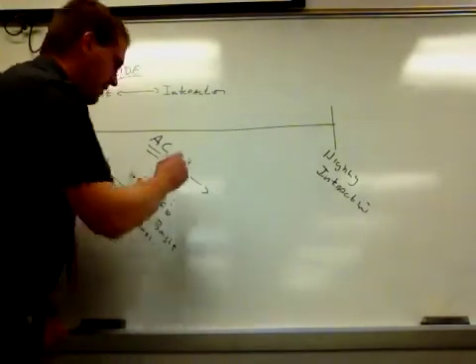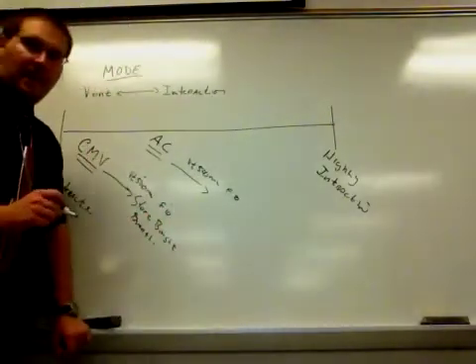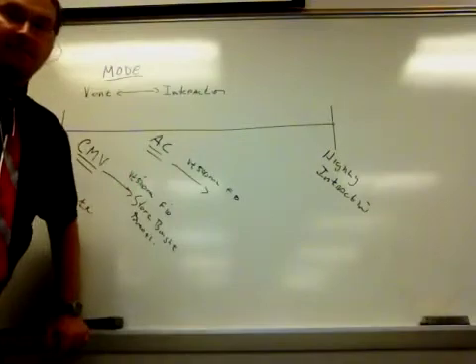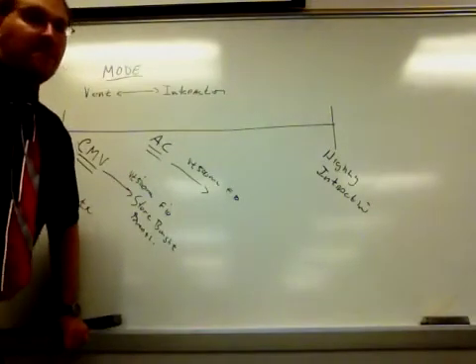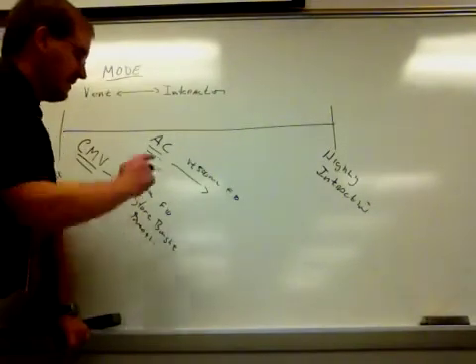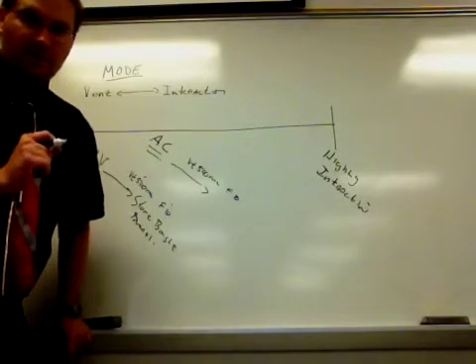Assist control is just like CMV in that I have a mandatory tidal volume. We'll keep it in volume control, but it could be pressure and a rate. If I set tidal volume and a rate in assist control, that patient will get that tidal volume and will get that 10 breaths a minute that we set. That is mandatory. The patient has to get that.